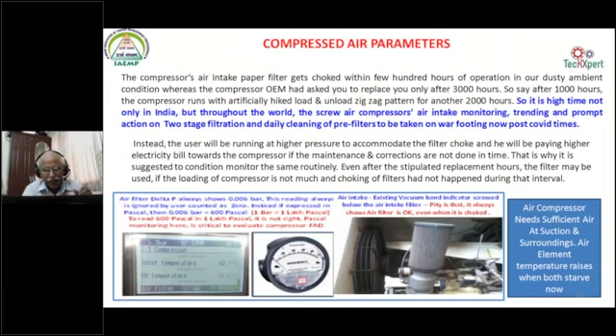We can see the right bottom figure. They have put a vacuum type yellow and red gauge. These band gauges, which are fixed on the pipeline filters fitted on compressors, always work safe and always show a safe reading only. It is always green, it is safe only, but automatically it is choked inside. Let us have either a digital display like the one shown by a compressor OEM, or an analog gauge, but you need to have a visual alarm. Once the pressure drop is more, automatically it can give an alarm. So the air intake for a given compressor needs to be monitored. Let us have the monitoring done at this stage.